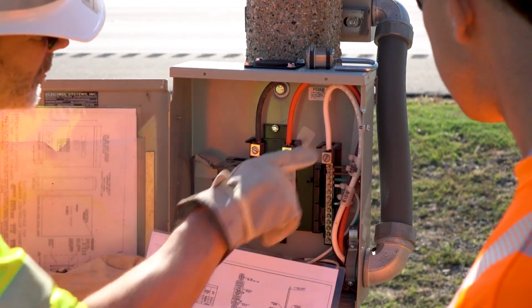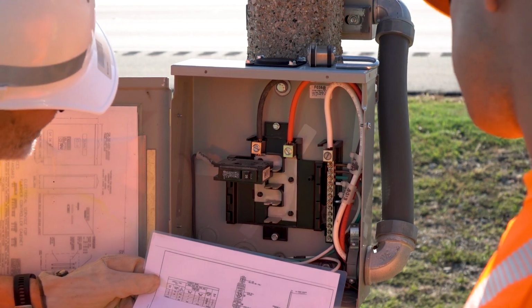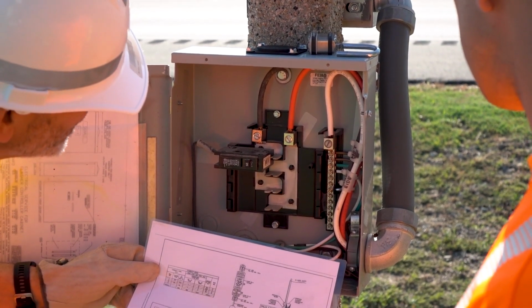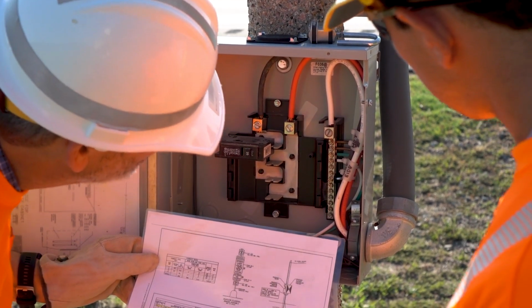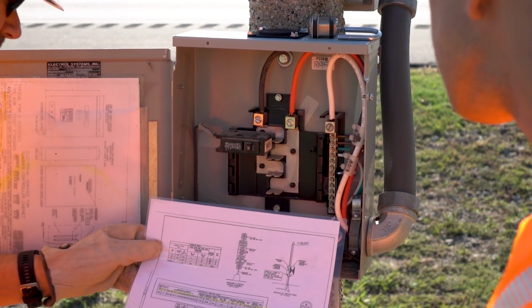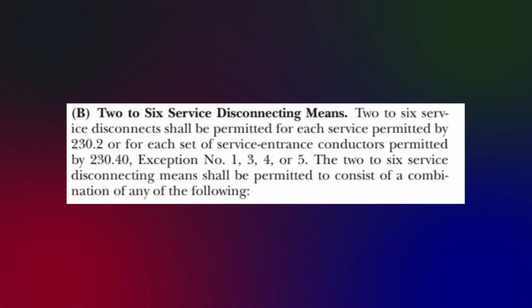Note that for a Type T service, the electrical service data sheet will not show the size of a main breaker, since the Type T does not have one. The NEC allows services with 6 or fewer branch circuit breakers to have no main breaker. This allows for a simpler and more economical service when only a few circuits are needed.